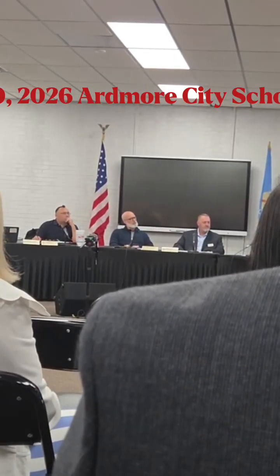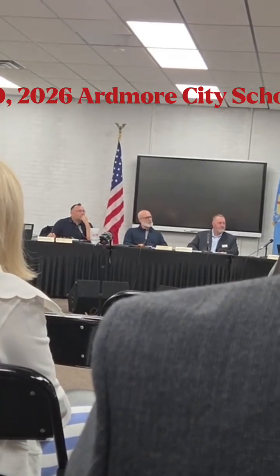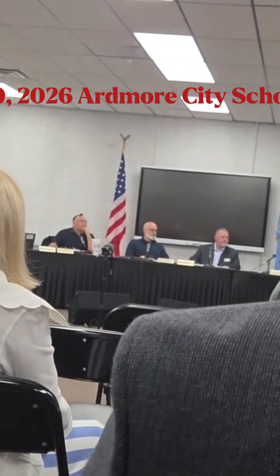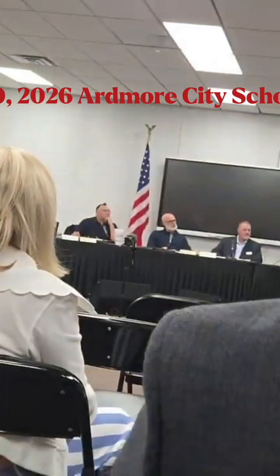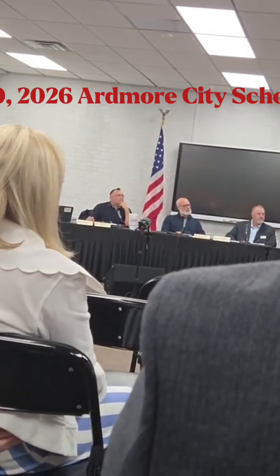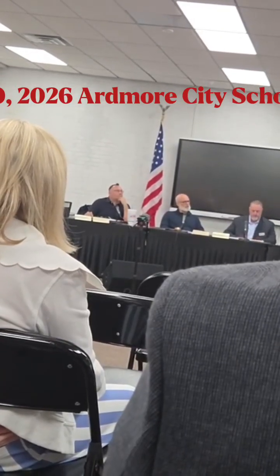So if you had a failure on a refrigerant-containing component in the system, it's getting close to the point where it's no more expensive to replace the unit than to repair it, just because R22 is like gold. It's very, very expensive. There are some substitutes that work very well and are less expensive, but you're getting an older and older system. Even the refrigerant that replaced R22, 410A, got obsoleted last year, and now there's a whole new refrigerant. They're constantly chasing refrigerants with less global warming impact. I don't know how long it'll be before the next one comes in.